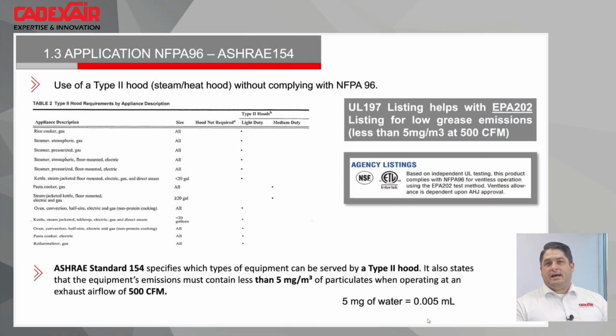Often people in the business also talk about a Type 2 hood. So what is a Type 2 hood? It's a hood for heat and steam. How do we know if equipment is for heat and steam, or is cooking or grease-producing equipment? If you are like me and read NFPA 96 with so much passion and wonder what to read after that, you can still read ASHRAE 154. I would say it's almost a better version than NFPA 96. I think it's easier to read and more straight to the point.